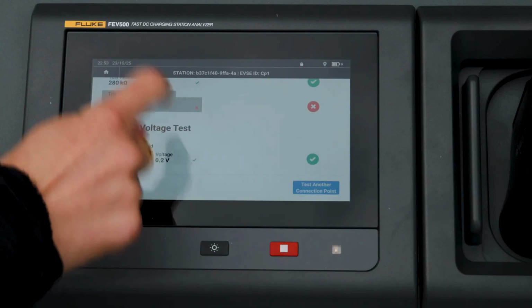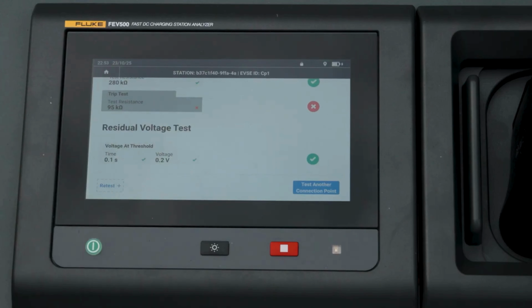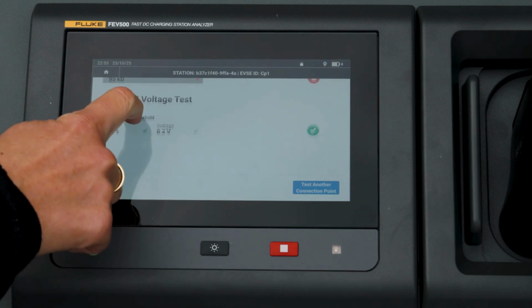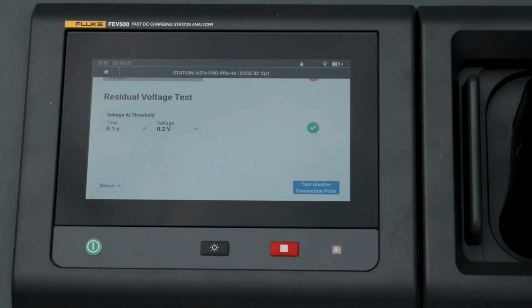So yeah, here we're seeing the failed IMD trip test because we didn't have an IMD. And then the last test is the residual voltage test that I was mentioning. Essentially, this is like a discharge voltage test, just making sure that once the charging session has been complete, that voltage is at a low enough safe level within a certain amount of time.